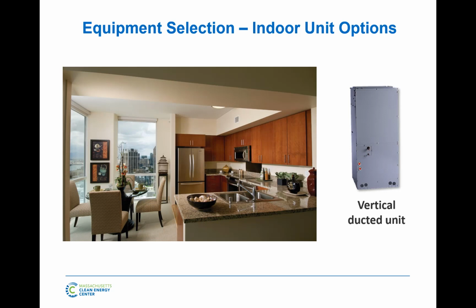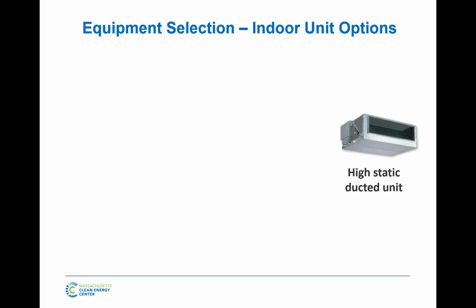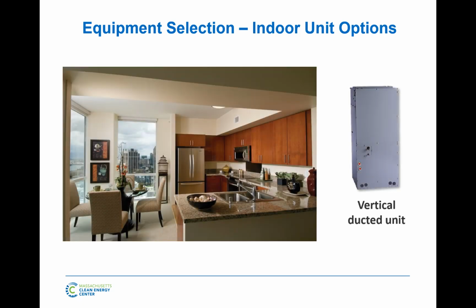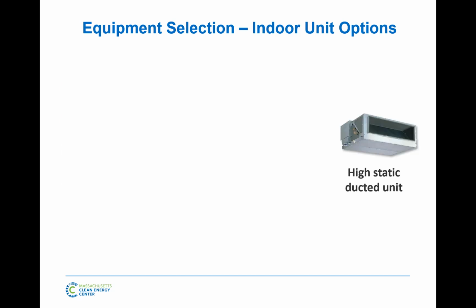Then on the ducted side as well, there are vertical ducted units. So these were like pancake style, horizontal ducted. Same concept with these vertical ducted units, just specifically made to match the North American market a little bit more. So think of the built-out corner in a multifamily residential unit that has your vertical stack heat pump or your vertical fan coil unit, this is a replacement for that. Similar to if you're looking at a single family home, these are basically furnace replacement type units that give you options when you're designing it. This would go in a closet or be built out in a wall, whereas this would go in a ceiling. And it all depends on what constraints you have in the building.